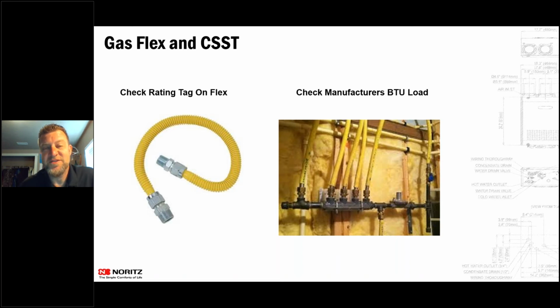I went to a house years ago where we walked up to the house and it sounded like an elk bugle going off inside of this house, and they had a gas flex that they got from Home Depot that was a 3/8 OD gas flex, and so it was pulling gas through there, and it was screaming as it went through that flex. So rule of thumb, a 7/8 OD gas flex is what you would like to see going through there. That's going to be able to handle that 199,000 BTUs or 180 or whatever that BTU load is. Just make sure that that gas flex that you have there will carry that load.